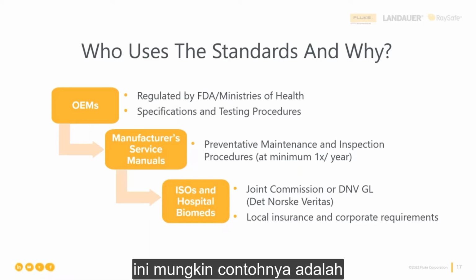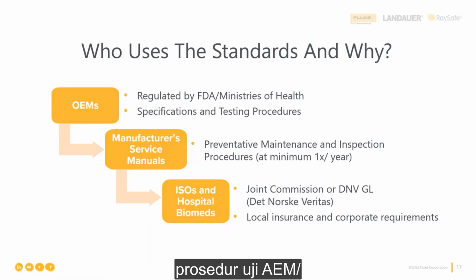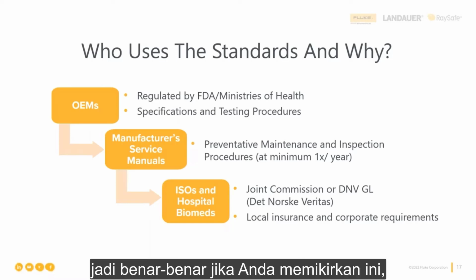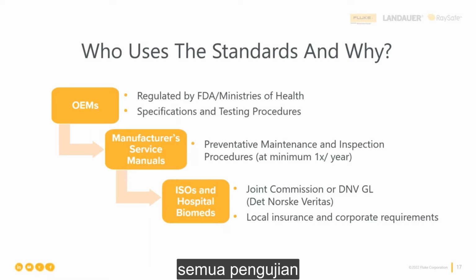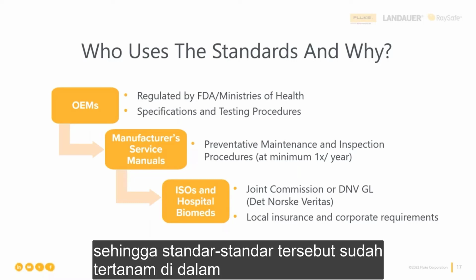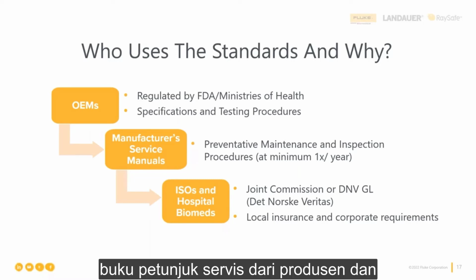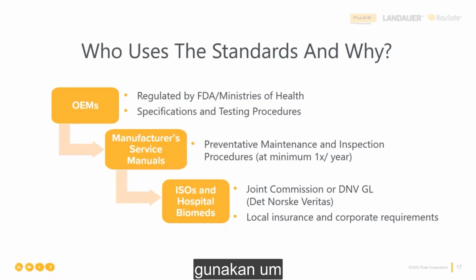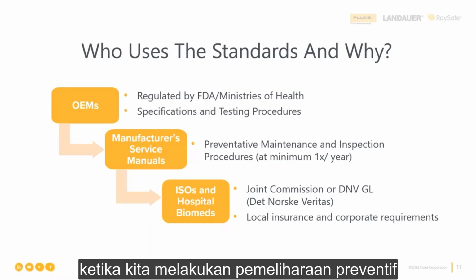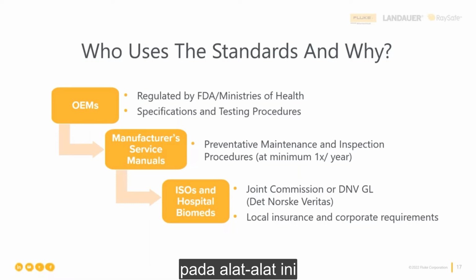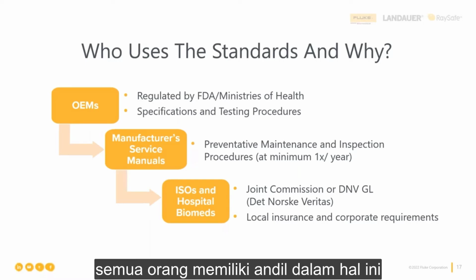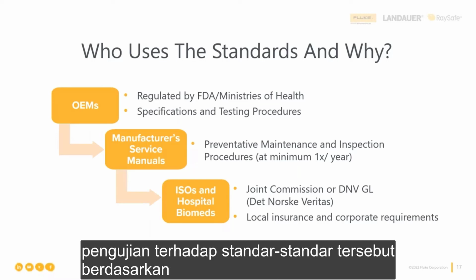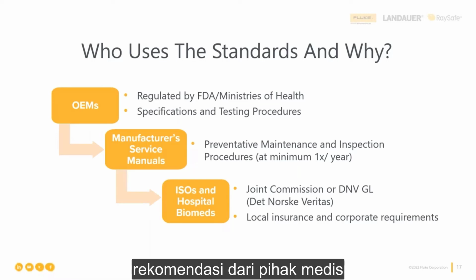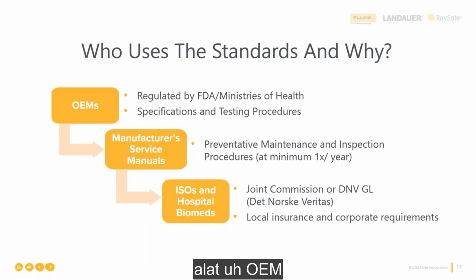An example of that might be an AEM test procedure, an alternate equipment maintenance. So really, if you think about it, all of the testing that you on the call today do circulates all the way back to the standards. The standards get built into the manufacturer's service manuals, and then those service manuals are what we use when we're doing preventive maintenance on these devices. So again, that's how everything stems back to the standards. Everybody has a hand in this, but really at the end of the day, we are testing to those standards based off of the recommendations of the medical device OEM.